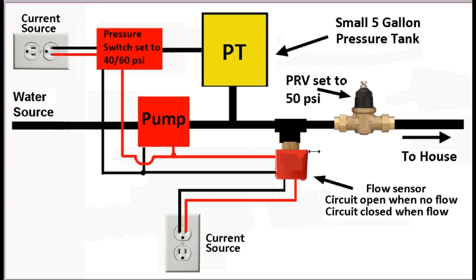The other case is you turn off the water, so the flow sensor detects no water, so that will be off, but the pressure switch could still detect that the pressure is below 40, and so it will continue to run the pump until the pressure tank reaches 60, and then it will turn off. Okay, and then it will be ready for the next time you use the water. You turn on the water. Okay, the pressure tank provides the initial flow, which turns on the flow sensor. The pump goes on, and it will stay on at 50 psi continually.